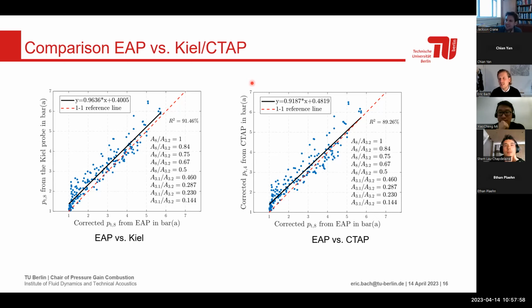Thanks. It's hard. That's the attractive thing about the CTAP or the Kiel probe method. For the CTAP method, I think the trend is also to use not one sensor location but multiple, and then bring them together into one plenum to have this pre-averaging of the data. But for the Kiel probe, you really just stick it in wherever location in your flow path you want, and then you can directly get some data. This is a very pragmatic way of getting this.